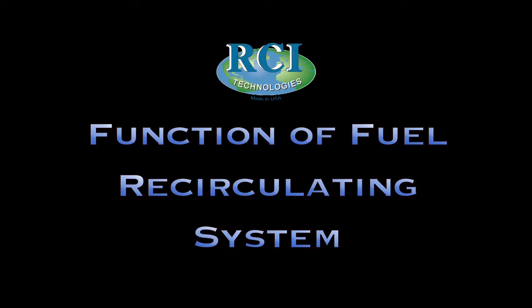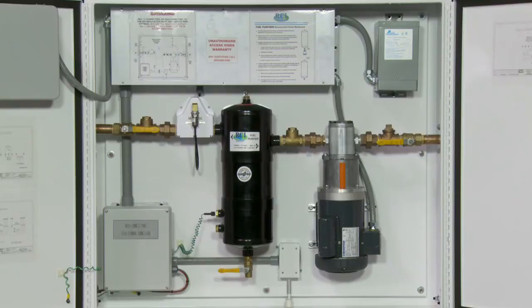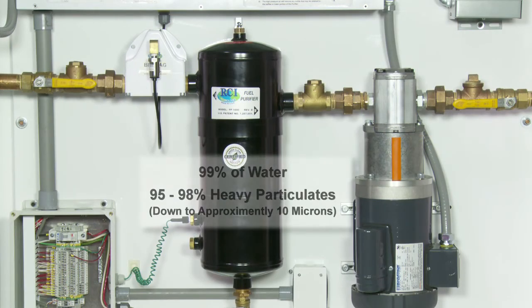The function of the fuel recirculating system. The FRS provides an efficient method of removing contaminants, including water and numerous other heavy contaminants common to stored diesel fuel. After the diesel fuel has been run through the FRS, the clean fuel is returned to the fuel tank. The RCI purifier removes 99% of water and 95 to 98% of heavy particulates down to approximately 10 microns.